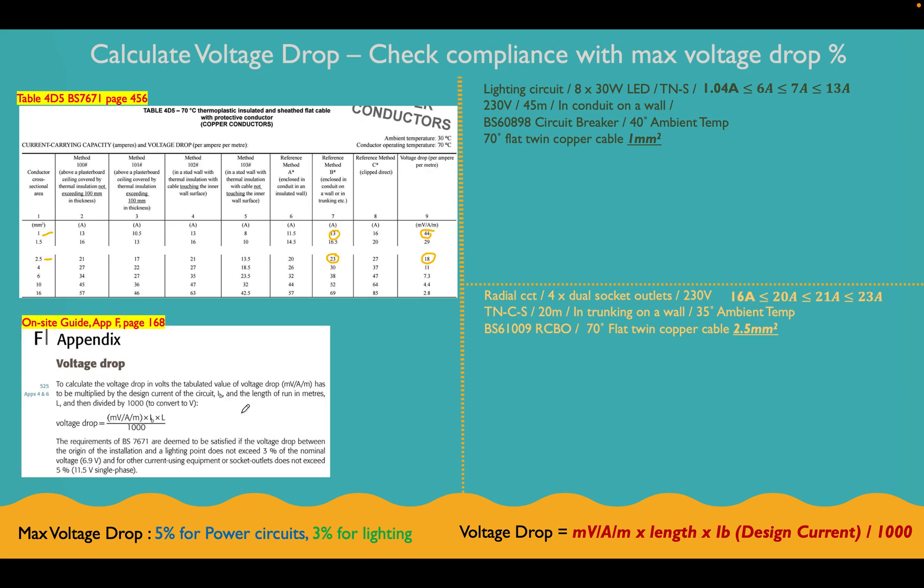This is really important, this bit here. So this is always in your on-site guide. And this is how to calculate the voltage drop. Okay, so you don't need to remember this. This is always in there. What we do need to be aware of is this bit at the bottom, the maximum voltage drop for lighting and for power circuits.